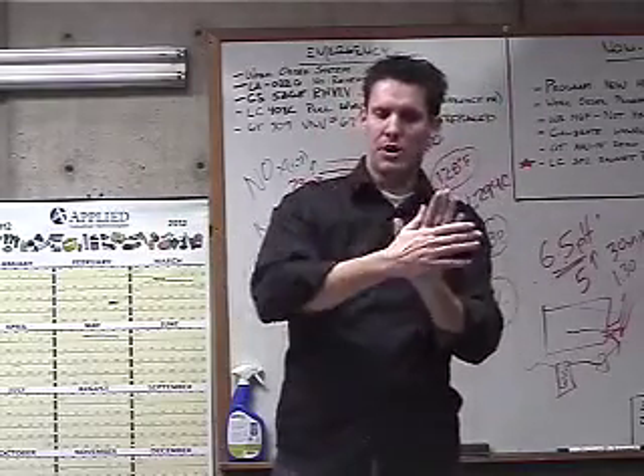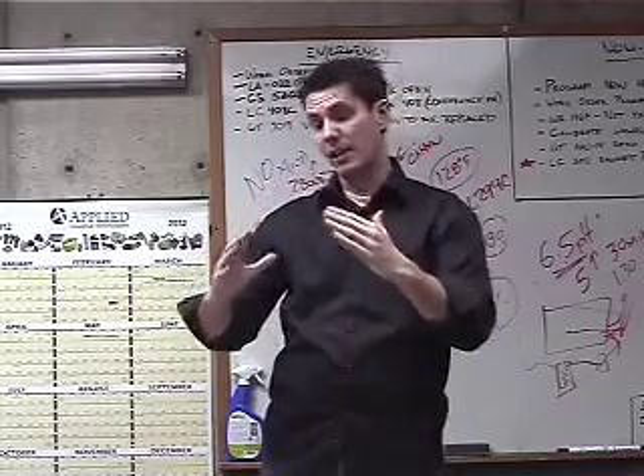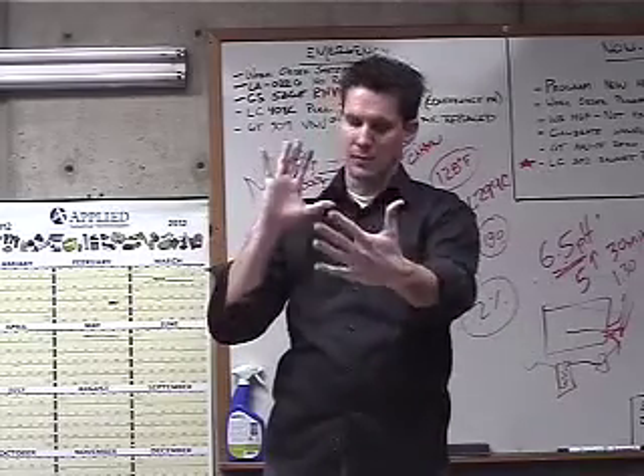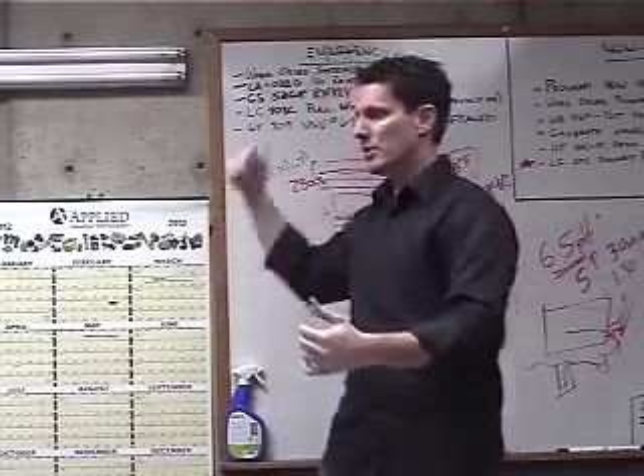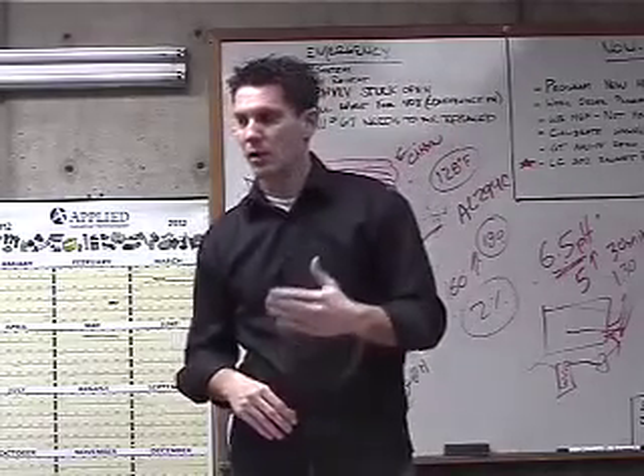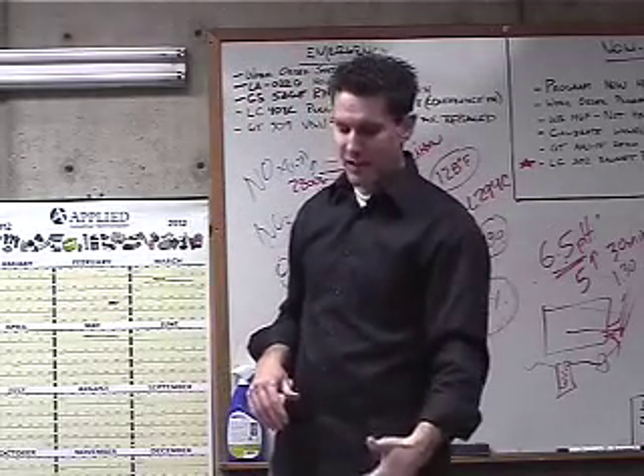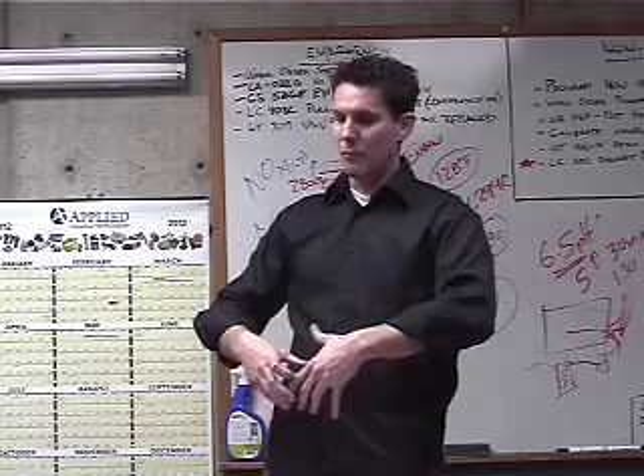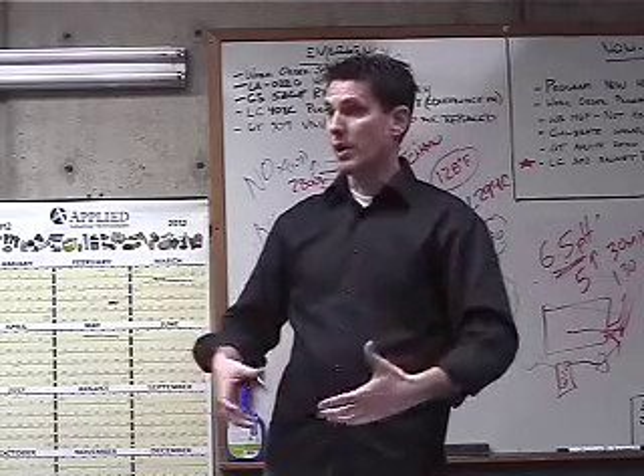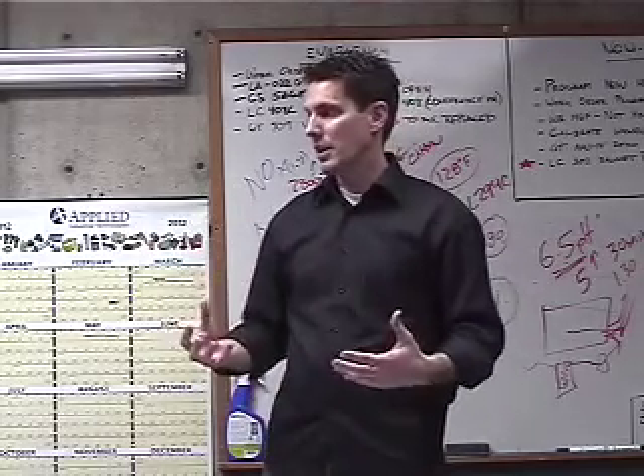And the boiler door that it blew off, there was a man ladder, luckily not a man, but a man ladder in front of it. It was permanently encased in that boiler door that was 2 buildings away. So when a boiler blows, the problem with the high limit is that water will start to boil potentially, and if it starts to boil, you start to build up pressure.